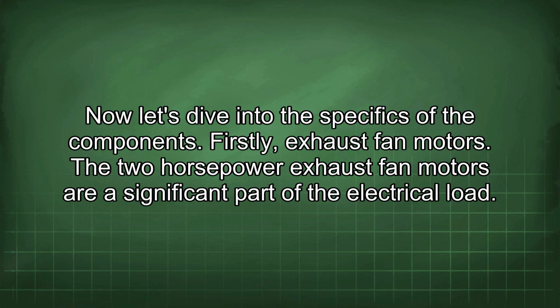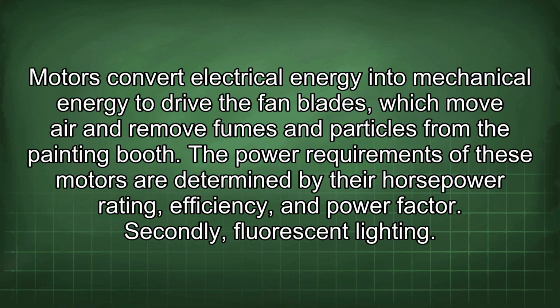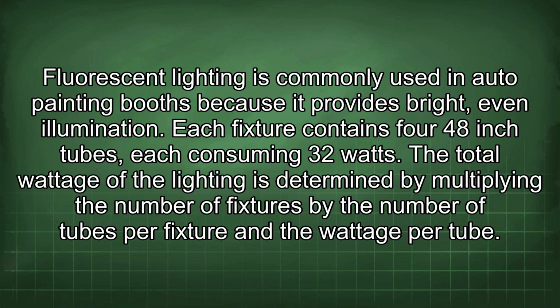Firstly, exhaust fan motors. The 2 horsepower exhaust fan motors are a significant part of the electrical load. Motors convert electrical energy into mechanical energy to drive the fan blades, which move air and remove fumes and particles from the painting booth. The power requirements of these motors are determined by their horsepower rating, efficiency, and power factor. Secondly, fluorescent lighting. Fluorescent lighting is commonly used in auto painting booths because it provides bright, even illumination. Each fixture contains 4 48-inch tubes, each consuming 32 watts. The total wattage of the lighting is determined by multiplying the number of fixtures by the number of tubes per fixture and the wattage per tube.